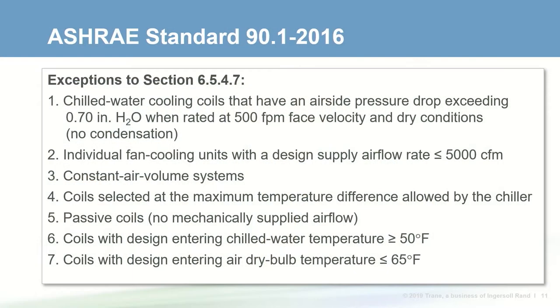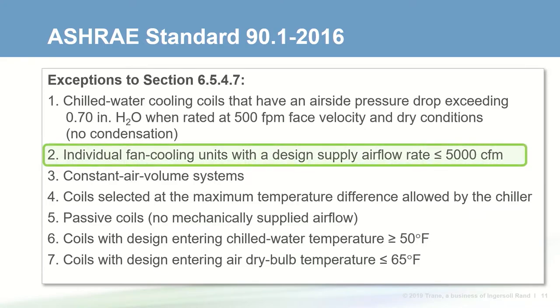While this is now a prescriptive requirement, like other sections of the standard, there are several exceptions. For example, individual fan cooling units that supply 5000 CFM or less are exempt — this includes fan coils, blower coils, classroom unit ventilators, and small air handlers. The committee included this exception because most small fan coils don't have an option for an 8-row coil. But as we'll see, an 8-row coil is not necessarily needed, so it's still a good idea to select even smaller units with a higher delta T.